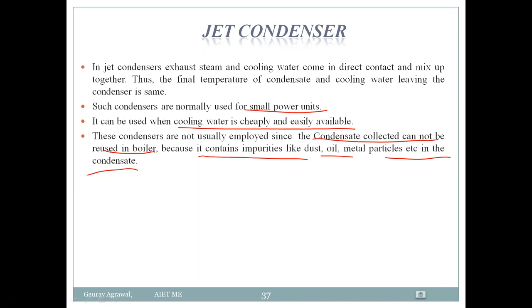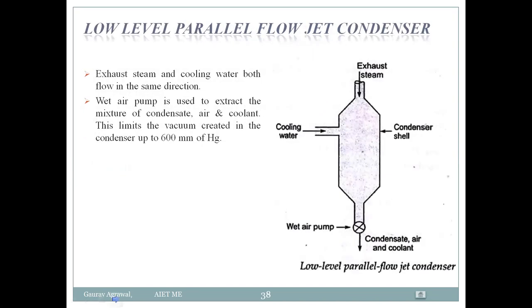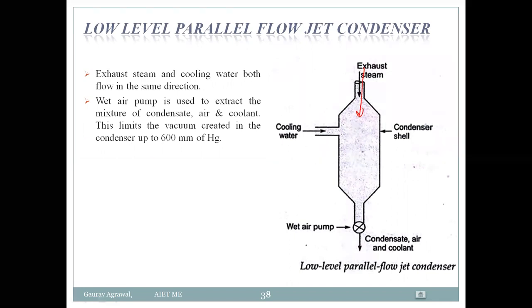Now let's look at the classification of jet condensers. The first type is the low level parallel flow jet condenser. In this condenser, the exhaust steam enters from one side and the cooling water also enters from the same side, meaning both flow in the same direction — this is the parallel flow arrangement.